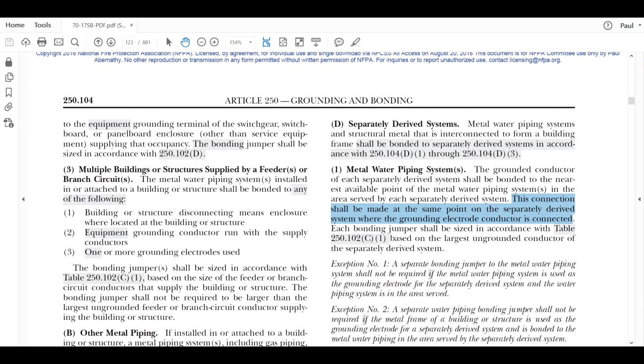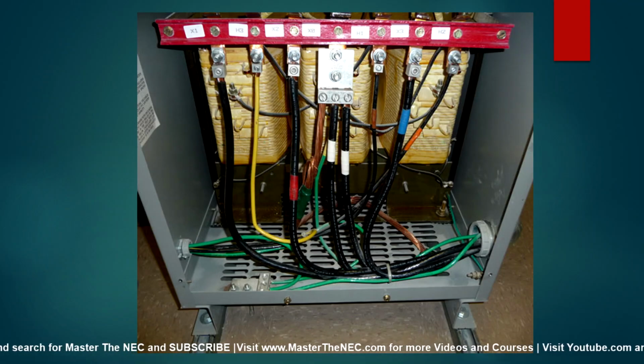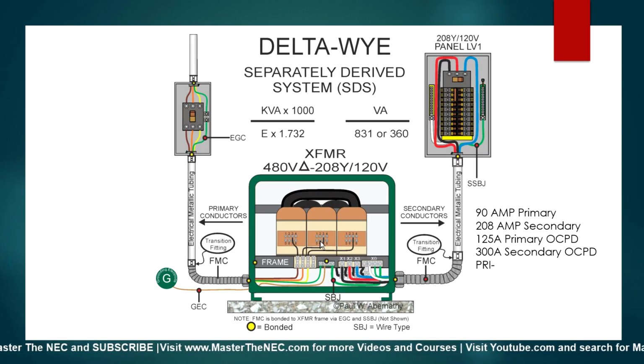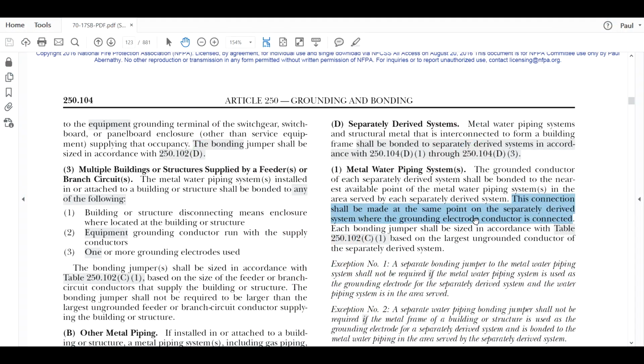Okay, so in our case, let's look at the graphic. So based on that rule, and let me go back here, excuse me, while I get us back. All right, it could be here, because that's where that's made, or it could be over here on the XO. Okay, these are an intimate connection. Okay, they're intimately connected. Now, I could have a bigger bus with everything going to the XO, and all of these could be one, but that's what we're dealing with here. Oops, sorry about that. All right, so we've established that. So it can be made there, but literally it has to connect the grounded conductor to the metal water piping system, and it is allowing that it shall be made at the same point where the grounding electrode conductor is connected, and we showed where that was in our graphic.